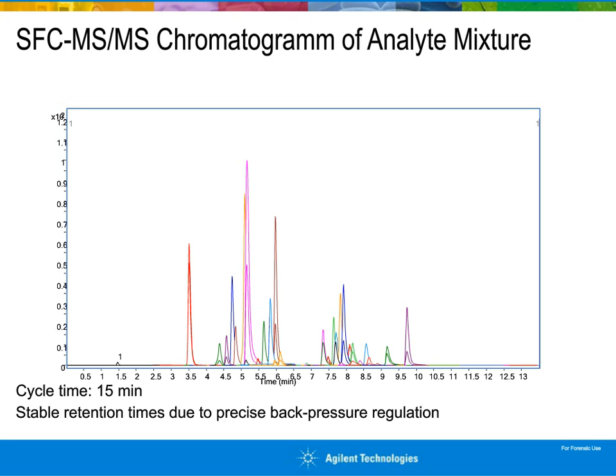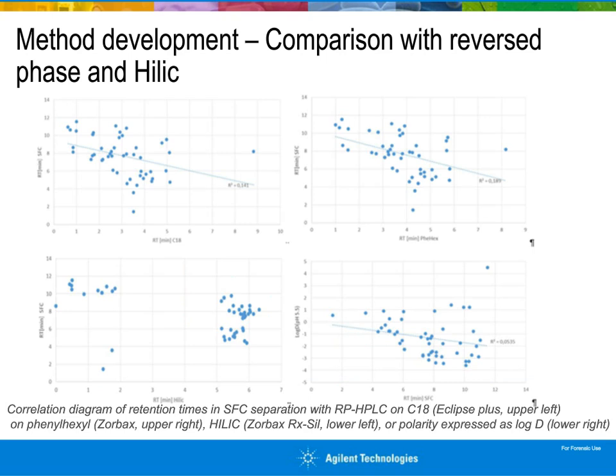given. With the more modern systems, the back pressure regulation, which has to do partly with the hardware and partly with electronics that is faster and can make more decisions at the same time, helps to keep the back pressure very stable in order to be able to use an application like this in routine.